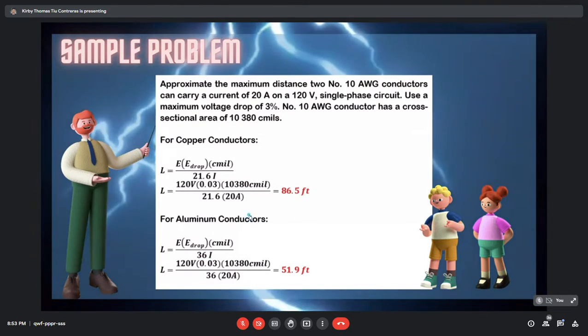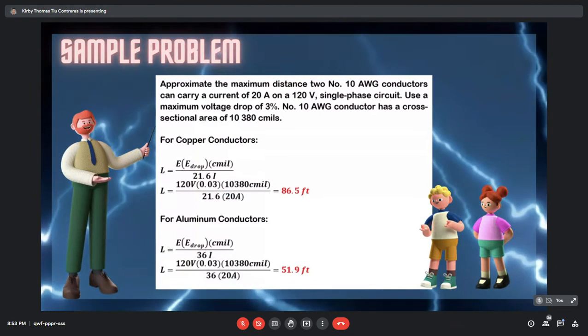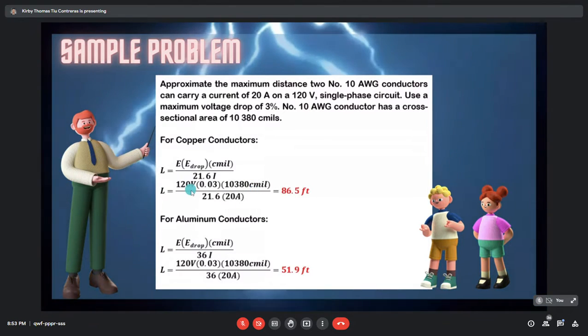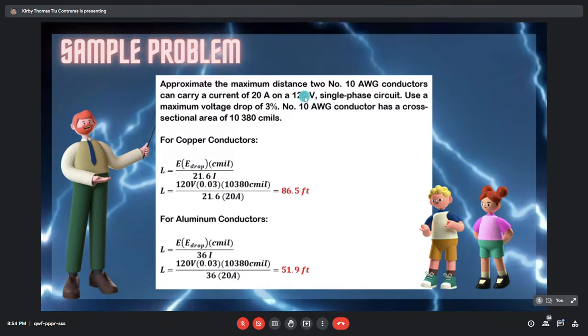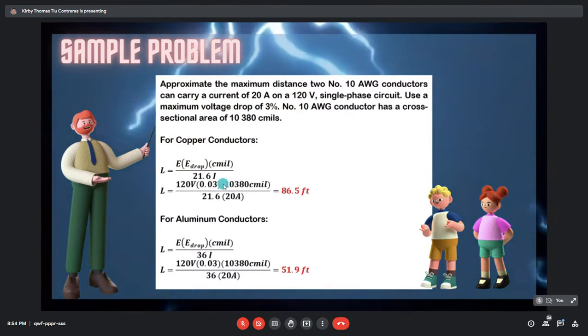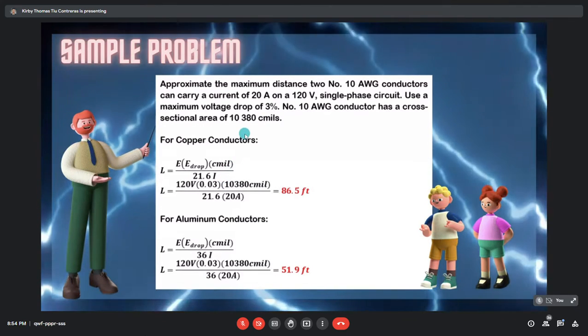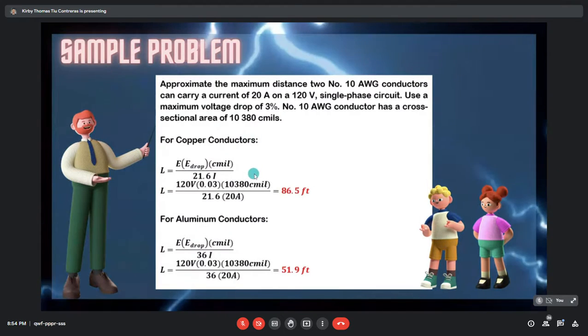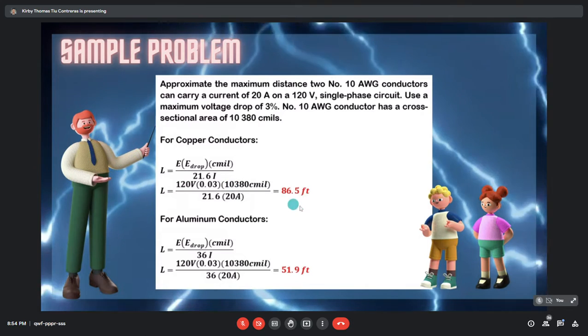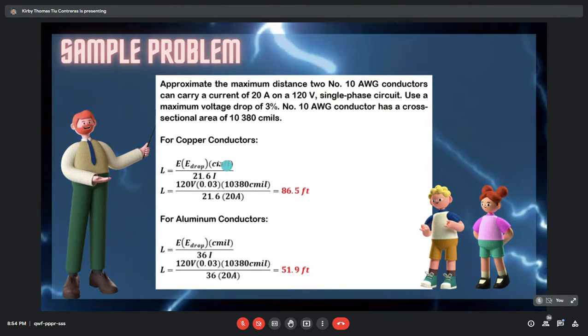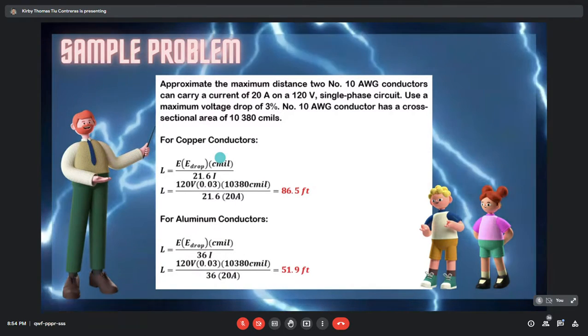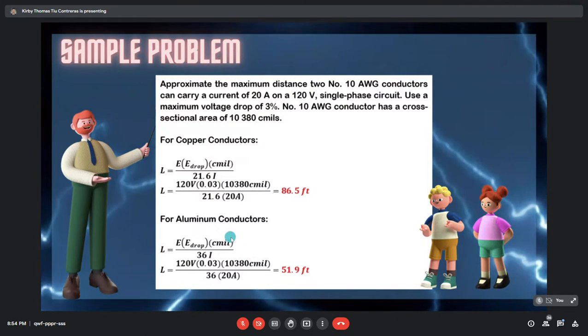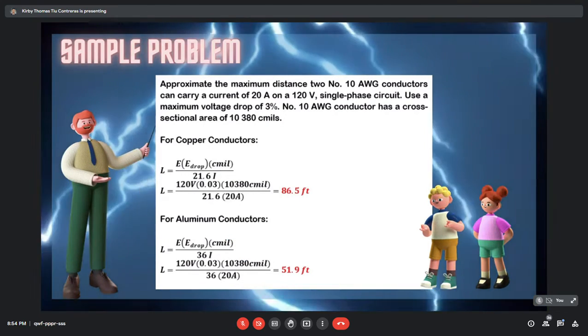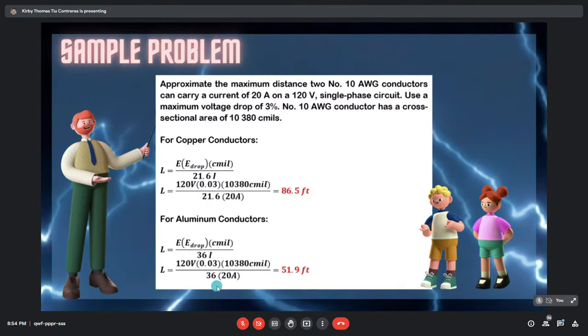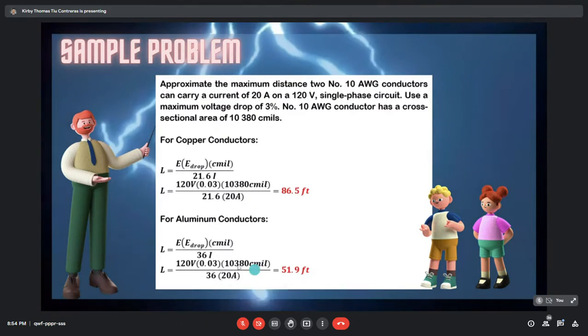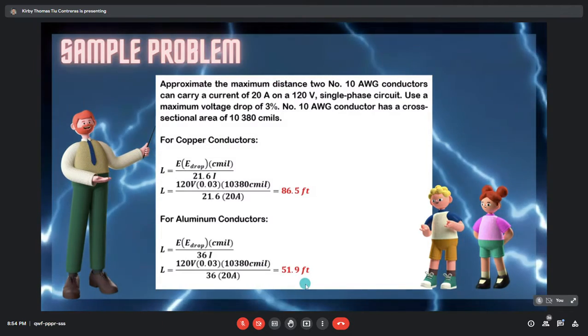So moving on, since the required values are given, we just do direct substitution. The voltage is given as 120 volts, and the voltage drop is 3%, so we convert it into decimal, 0.03. The circular mils is 10,380. Evaluating that, we'll get a length of 86.5 feet if the material of our conductors is copper. Proceed to aluminum. It is again direct substitution of the given values. It's just that the resistance constant is 36. Evaluating again, we'll get a 51.9 feet length.